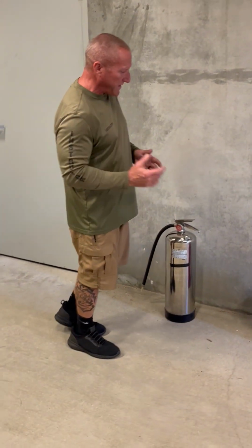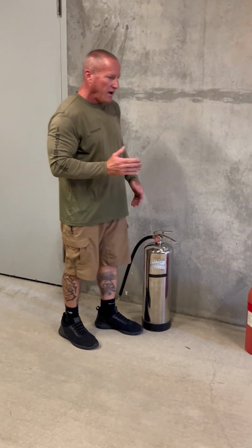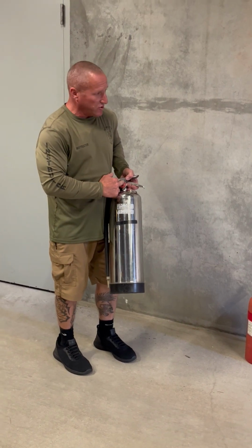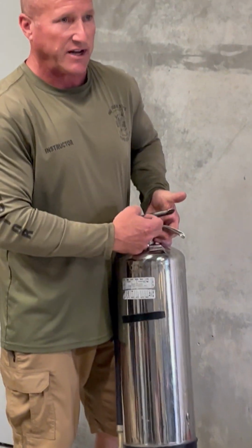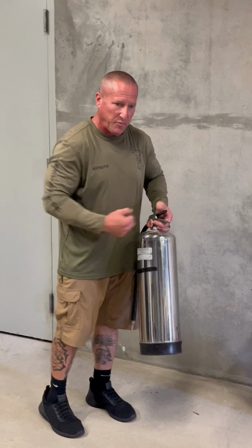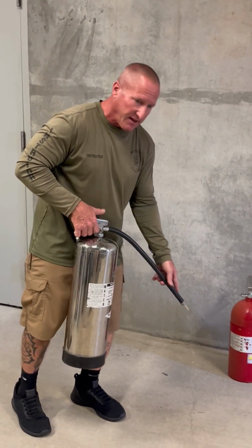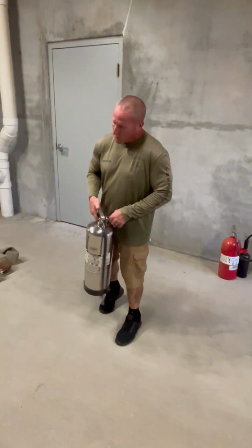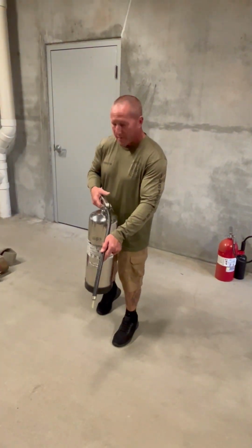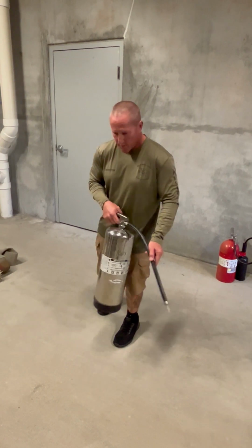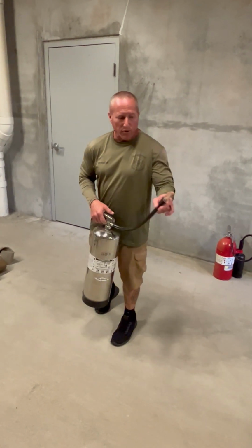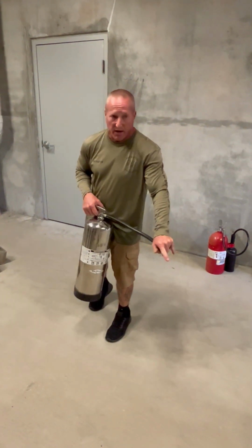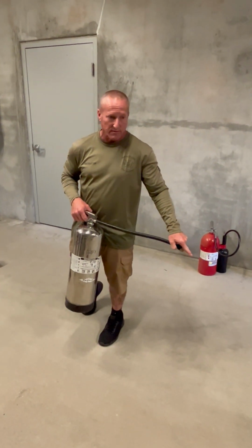So if I were to pick my extinguisher and I had an ordinary fire, I could grab my A. I would verify that my gauge was in the good range. It should be sealed. It should have a pin. I would remove my pin. I'm always going to test it, and then I would apply the PASS method. So I'm going to basically pull the pin. I'm going to aim at the base of the fire, squeeze and sweep until the fire is out. With a water extinguisher, I can take my finger and put it over the tip and use it like a fan spray to distribute that material also.